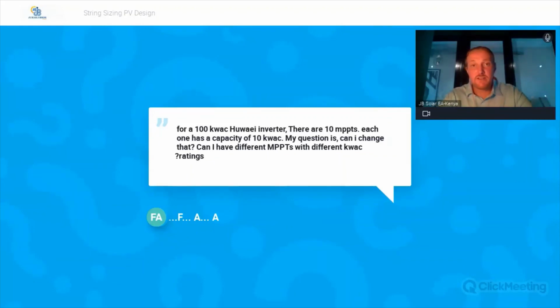Okay, you're mistaken. The MPPTs do not have a capacity of 10 kilowatts AC. That's not how it works. The 100 kilowatt AC inverter does have 10 MPPTs, but there is no kilowatt capacity rating on each MPPT. The limit is the current. There's a limit on the current per MPPT, not the kilowatts per MPPT. So you can have different MPPTs with different kilowatt rating. You can. That's totally fine. But the MPPTs are not limited by the kilowatt. They're limited by the voltage and the current. There's the max volt, there's the operating voltage range and the max current.